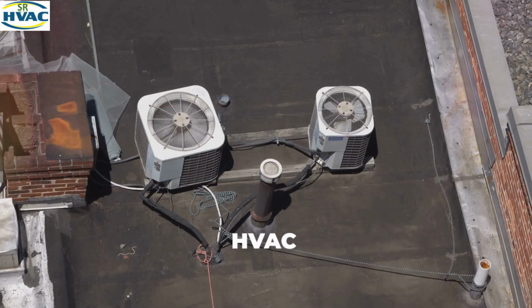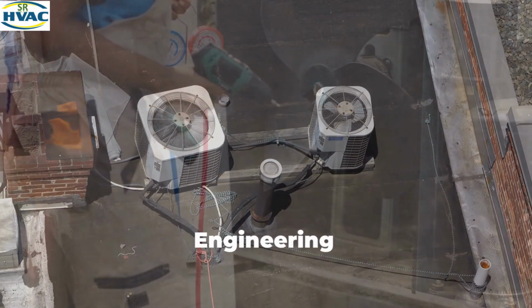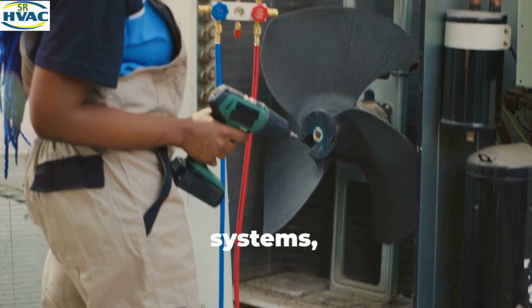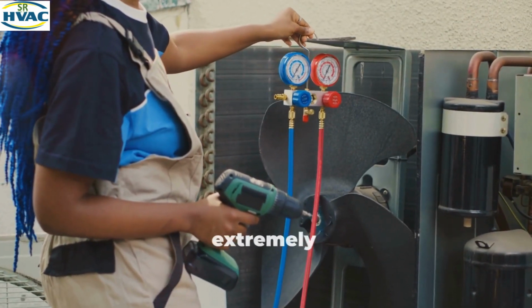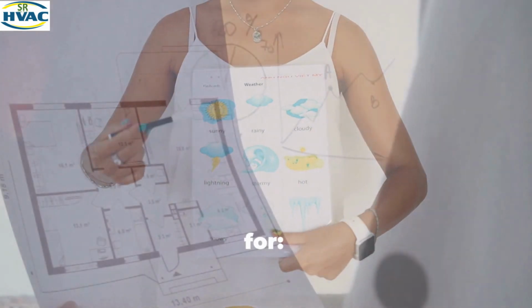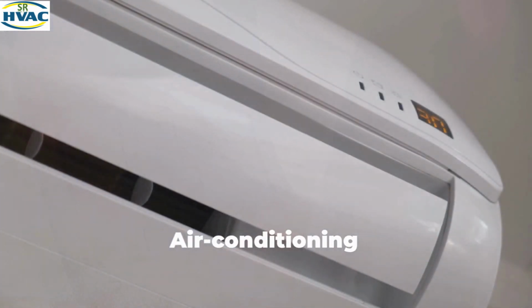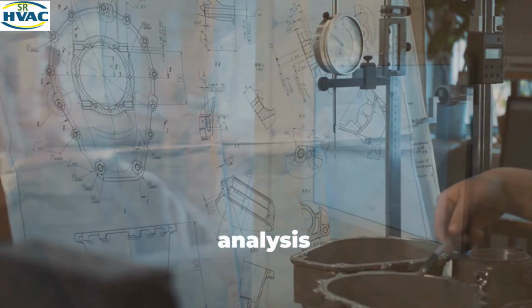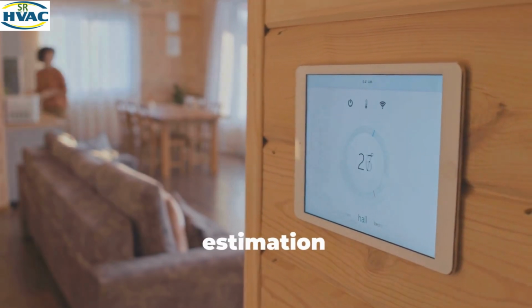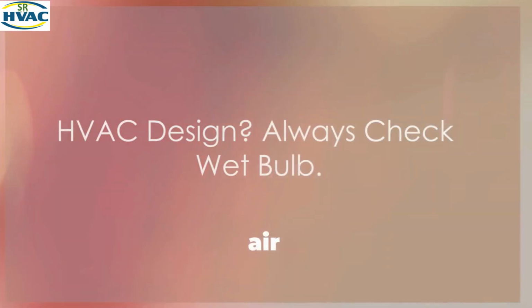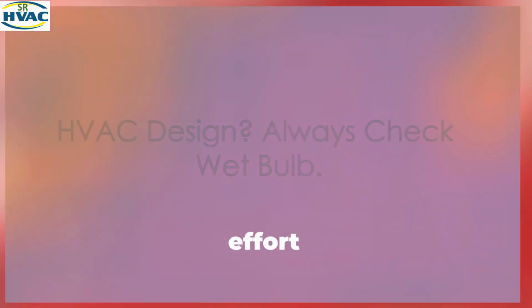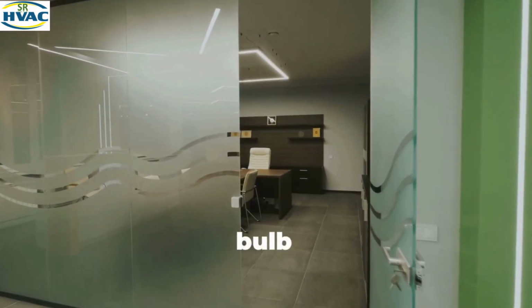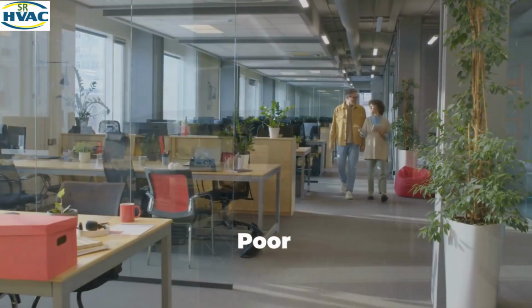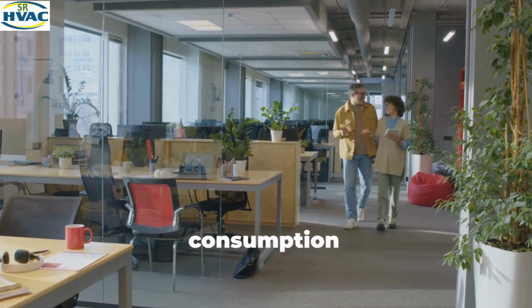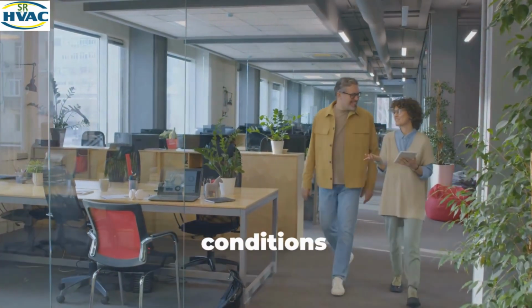Importance in HVAC and engineering. In HVAC systems, wet bulb temperature is extremely important. It is used for cooling load calculation, air conditioning design, cooling tower performance, psychrometric chart analysis, and indoor comfort estimation. Dry bulb shows air heat; wet bulb shows the cooling effort you must plan for. Ignoring wet bulb temperature can lead to poor cooling, high energy consumption, and uncomfortable indoor conditions.